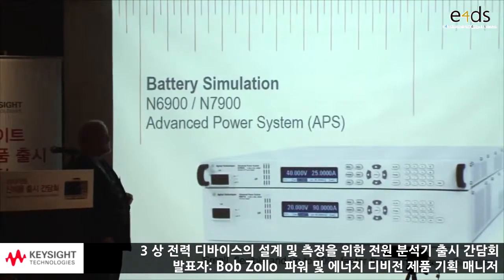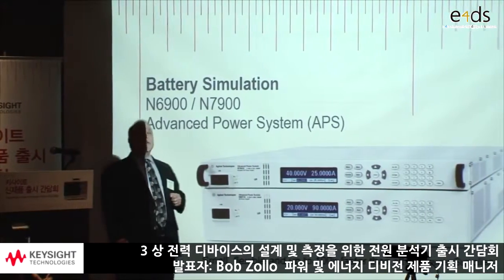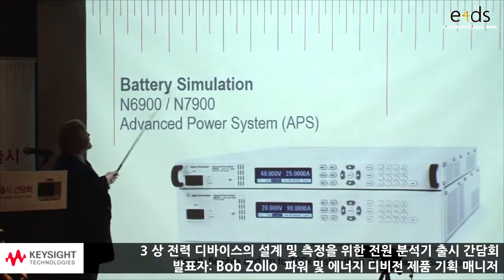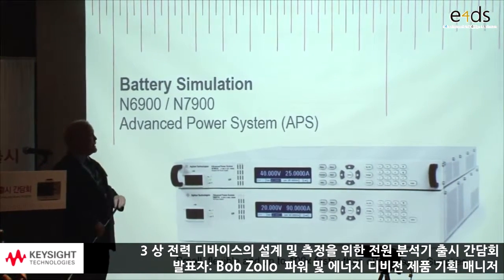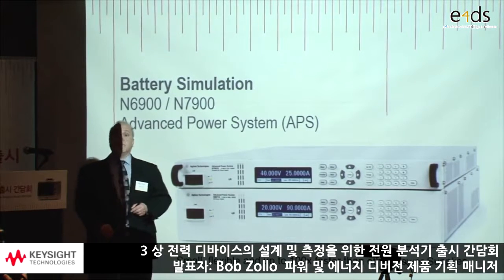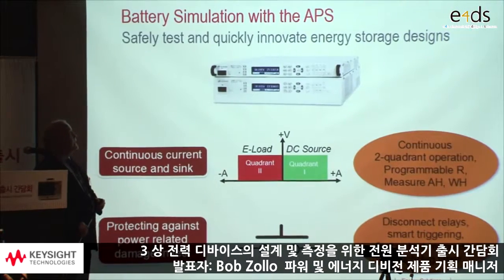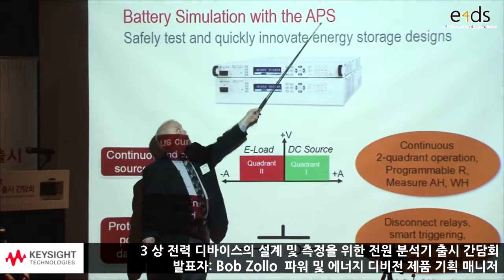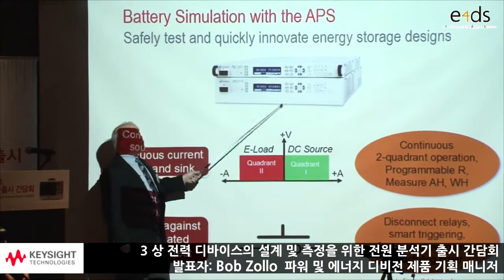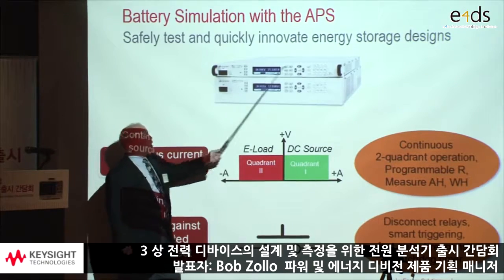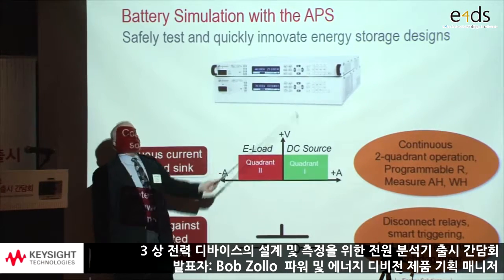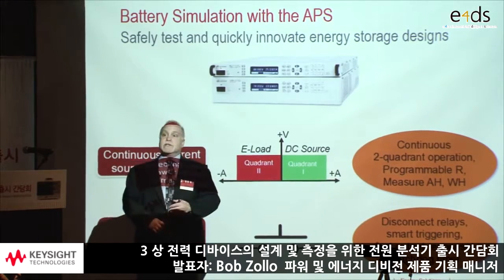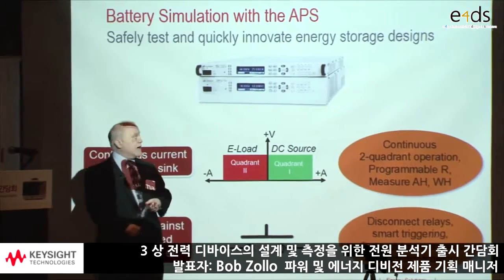Next slide. The next quick example I'd like to show is with respect to storage technologies. That is a battery simulator based on our advanced power system. Next slide, please. In this case, the battery simulator is based on our APS, Advanced Power System. And we have several different models in our family. There's a 1 kilowatt version and a 2 kilowatt version, and these can be put in parallel to make larger, higher powered systems to simulate larger batteries.